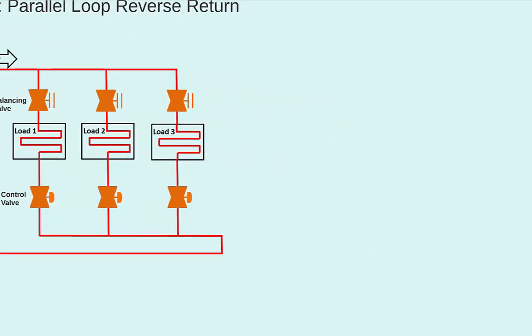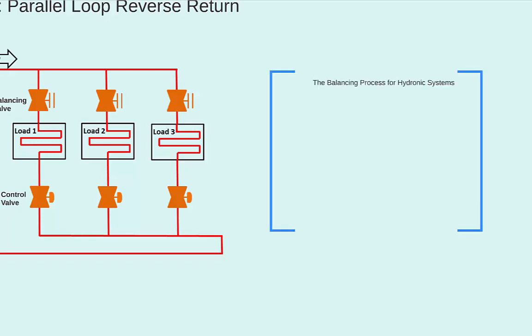Now, this process of adjusting all the balancing valves to ensure the right amount of flow is getting to each coil is literally called the balancing process. It is performed by a testing, adjusting, and balancing, or TAB, subcontractor after the system is installed, but before the occupants move into the space the system serves. It is often reaccomplished at various times throughout the life of a building, especially when the function of the building has changed or a portion of the HVAC system has been renovated.